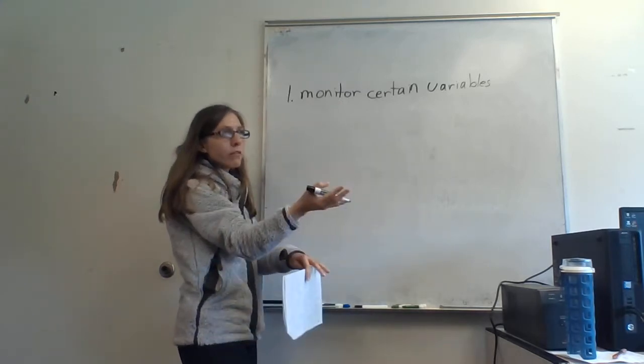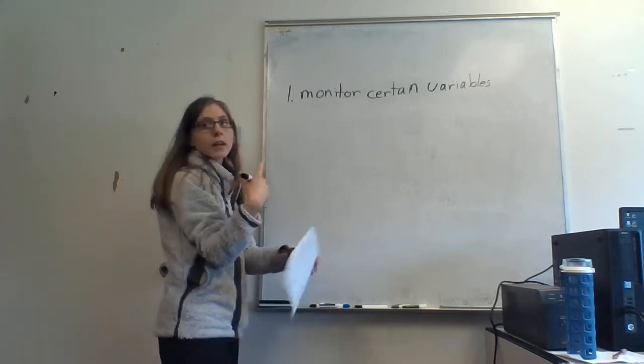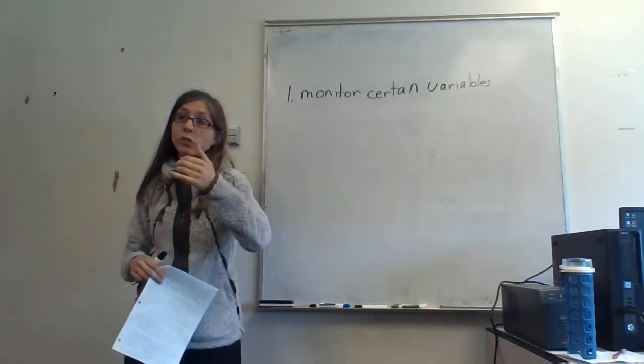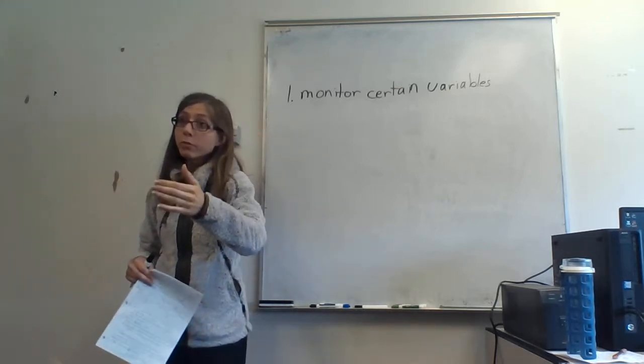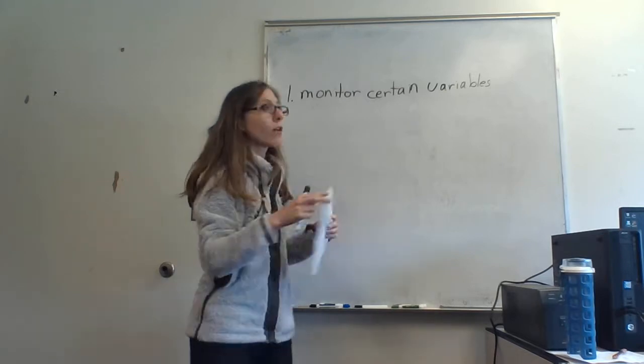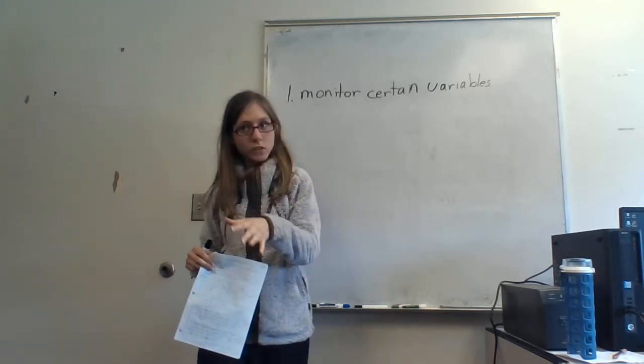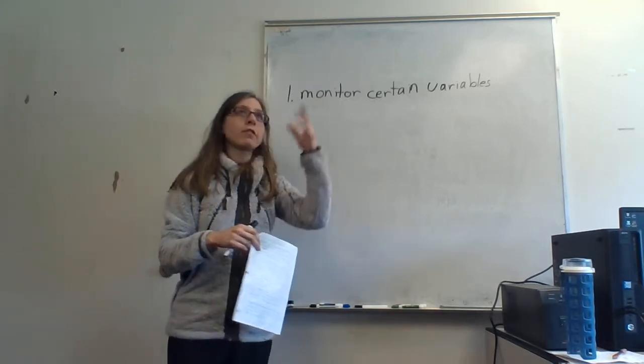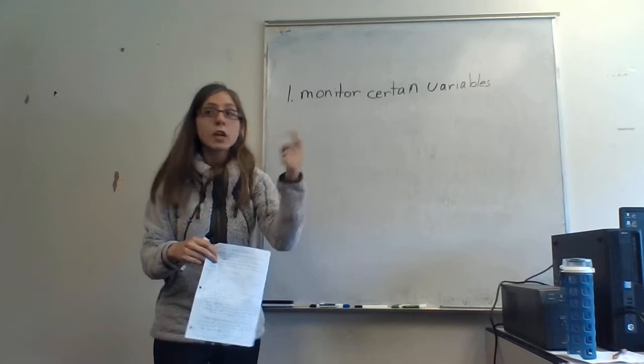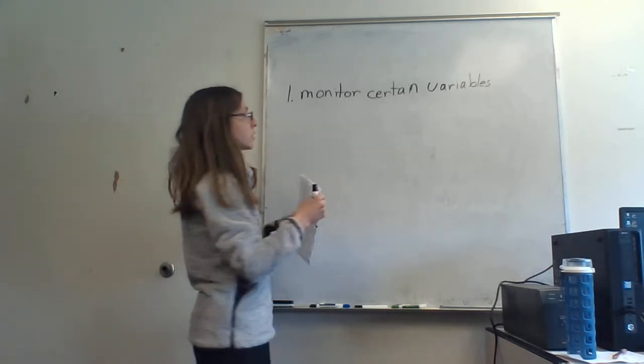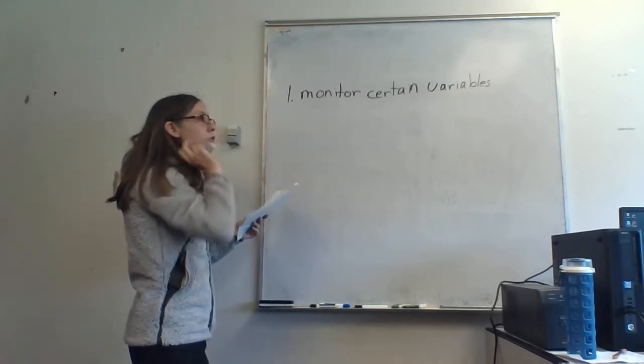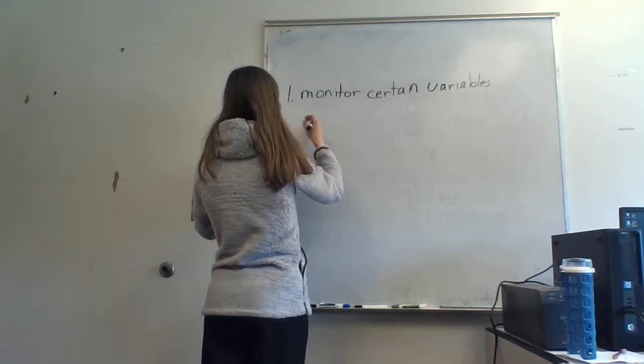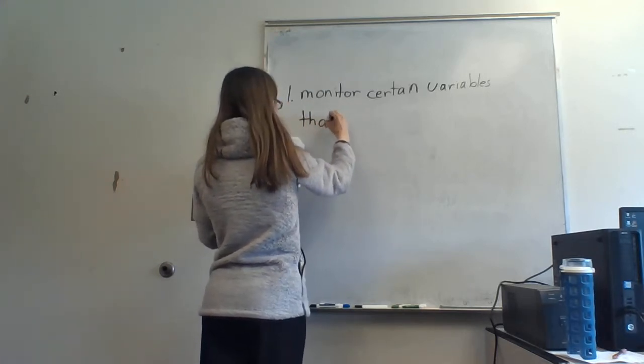You would choose certain key things where, if you knew the value, you'd be sure you're okay based on what you expect. For example, if a safety objective was that the temperature of your tubes could get too high, you'd say, well, I better measure the temperature somewhere. Based on your expectations as an engineer — this involves engineering judgment and design — you'd feel confident that if the temperature is always below a threshold here, you wouldn't expect it to be above that threshold elsewhere.